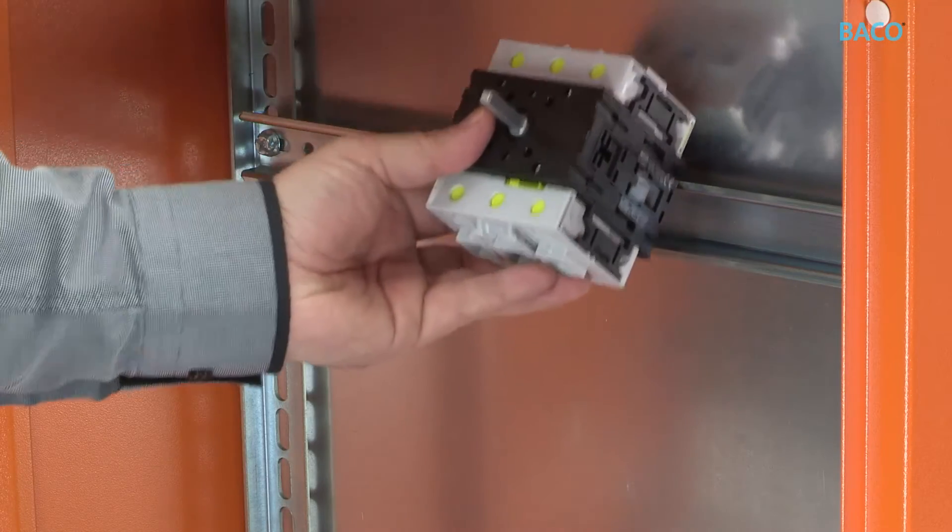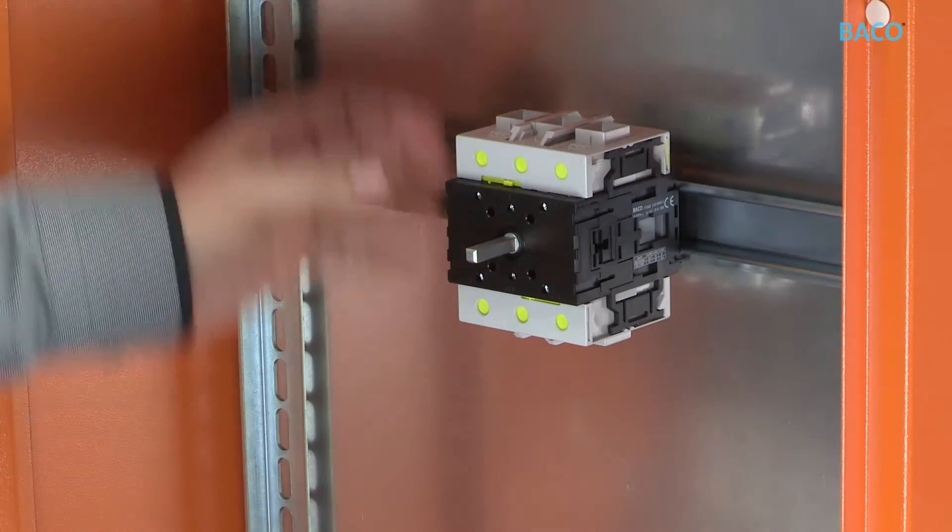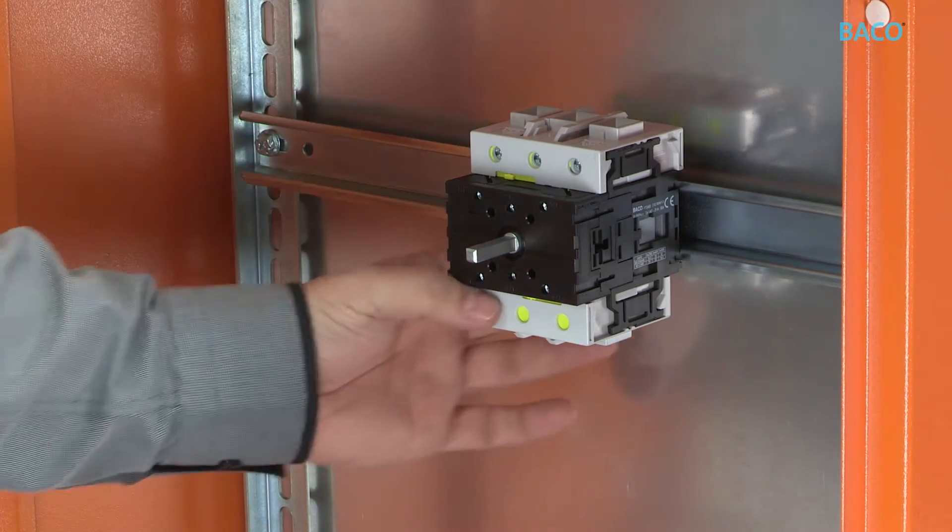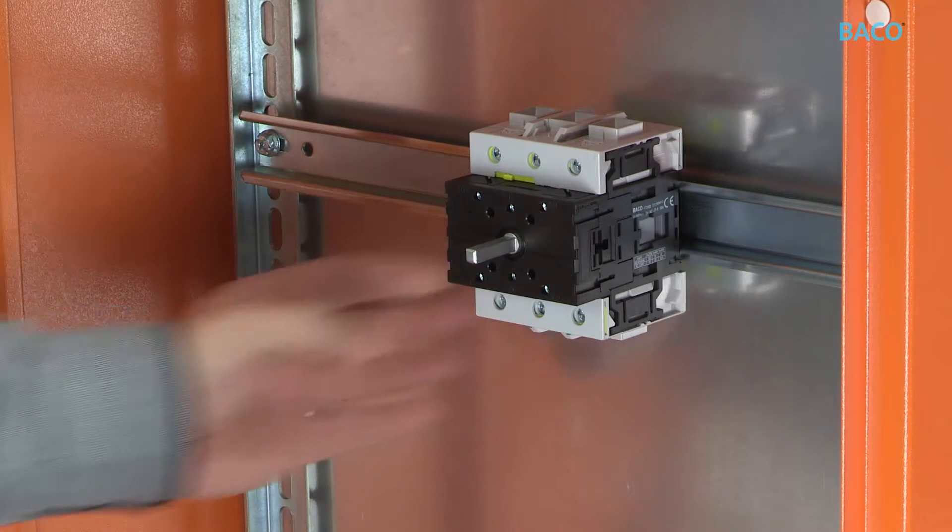For rear mounting assembly, take the three pole main block and slide the terminals to the front. Then snap it onto the DIN rail with a vertical circular motion.